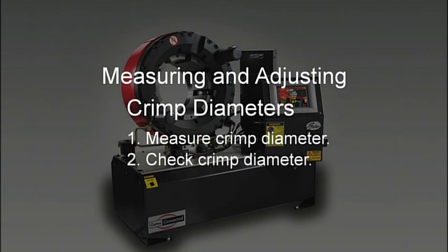2. Check crimp diameter. The measured crimp diameter must be within plus or minus 10 thousandths of the published crimp diameter. If the measured crimp diameter is too large, recrimp to the proper crimp diameter. If it is too small, then it must be discarded. 3. If necessary, adjust the crimp diameter. If the crimp diameter is not within the specified crimp tolerance, an adjustment to the crimp set point value needs to be made. To obtain a smaller crimp diameter, change the set point value to a smaller number. To get a larger crimp diameter, change the set point value to a larger number. Changing the set point value by approximately 0.02 will change the crimp diameter by approximately 1/1000th of an inch. After the correct crimp diameter is achieved, record this new setting in your crimp data manual for future reference.